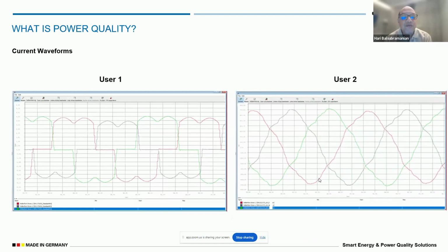So this is a very simple way of showing that harmonics can flow from one load or one consumer to the other, where they can affect the performance of the machinery for no fault of the linear load consumers. Yeah, this also has repercussions down below.